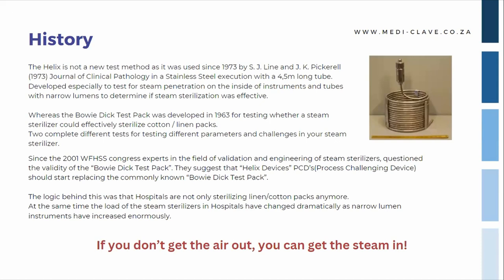The logic behind this was that hospitals are not only sterilizing linen or cotton packs anymore. At the same time, the loads of steam sterilizers in hospitals have changed dramatically. So that's when the lumens started coming in, the endoscopes, all the hollow objects. A standard Bowie-Dick test pack would not be able to get into hollow instruments. Today, the challenge of the steam sterilizers are these kind of complex, narrow lumen instruments. It is all about whether the steam sterilizer can effectively remove all the air and replace it with steam inside the hollow object. If you do not get the air out, you cannot get the steam in.